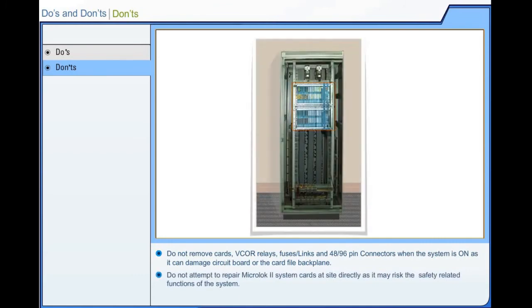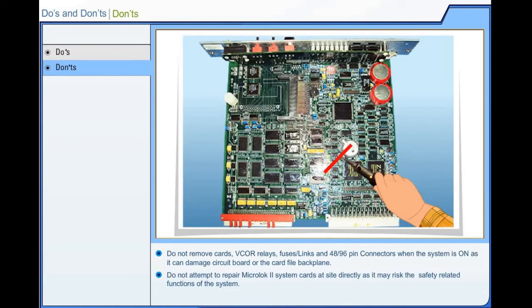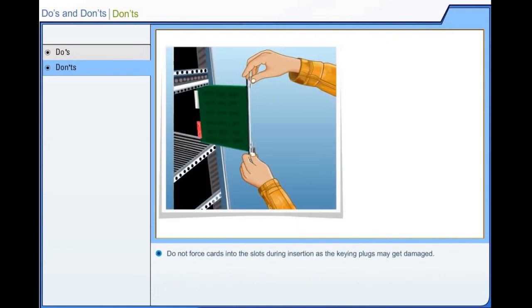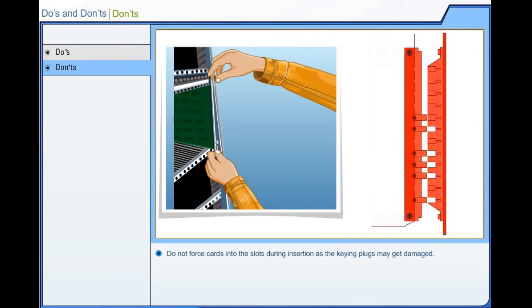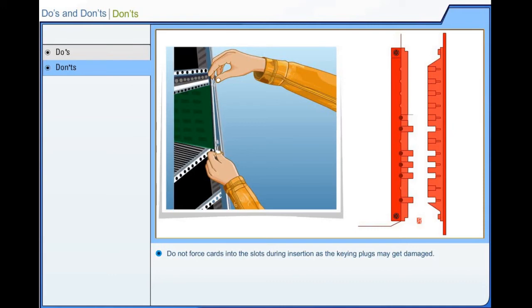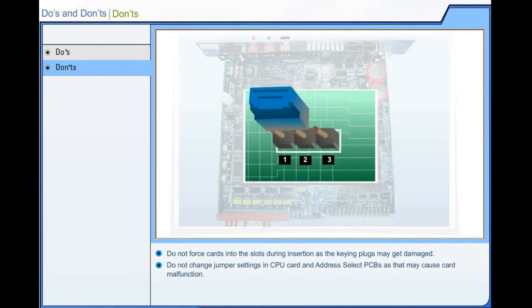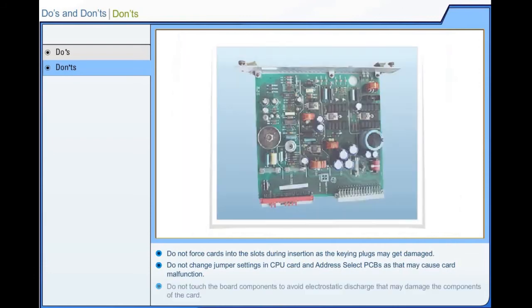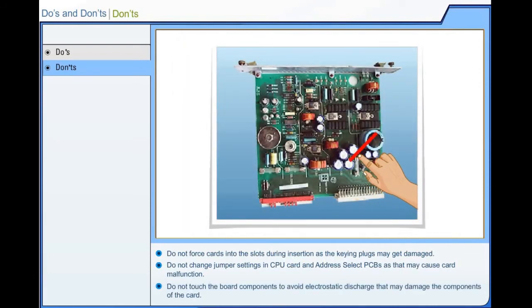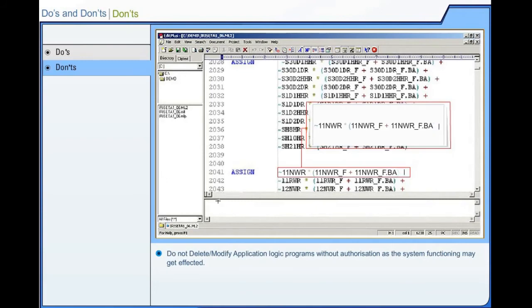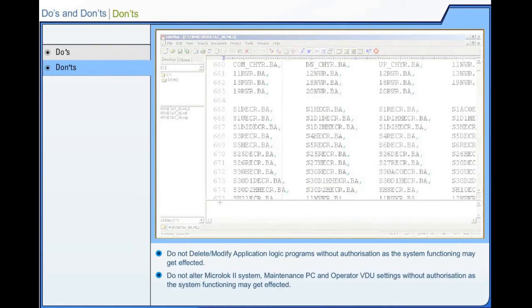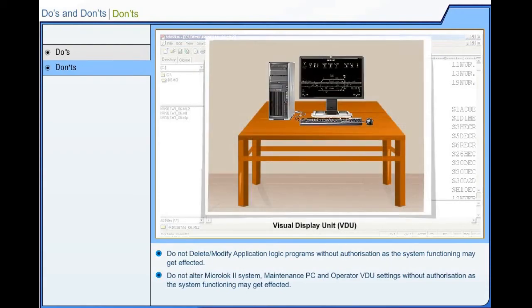Do not attempt to repair MicroLok II system cards at site directly, as it may risk the safety-related functions of the system. Do not force cards into the slots during insertion, as the keying plugs may get damaged. Do not change jumper settings in the CPU card and address select printed circuit boards, as that may cause card malfunction. Do not touch the board components to avoid electrostatic discharge that may damage the components of the card. Do not delete or modify application logic programs without authorization, as the system functioning may get affected. Do not alter MicroLok II system, maintenance PC, and operators' VDU settings without authorization, as the system functioning may get affected.